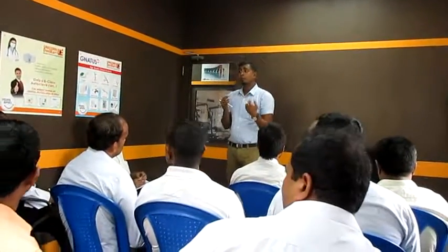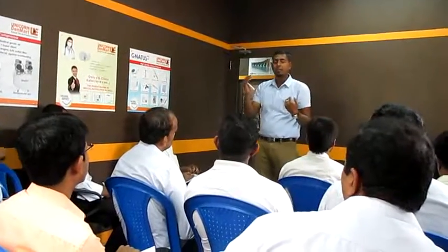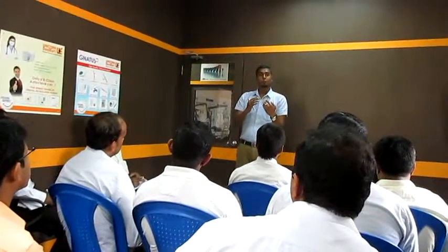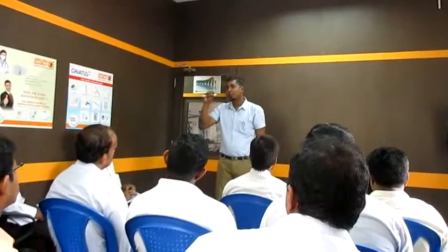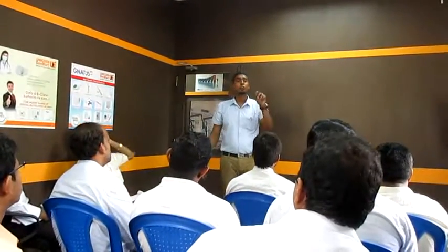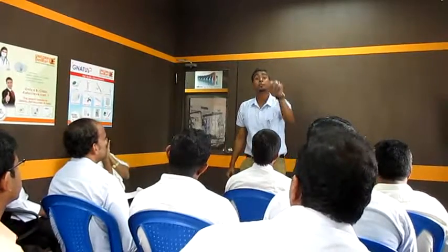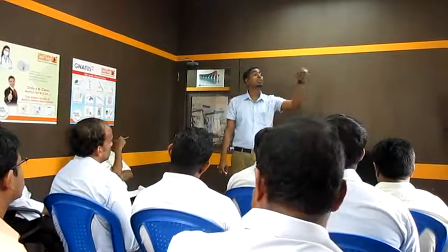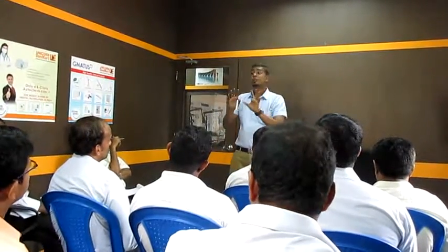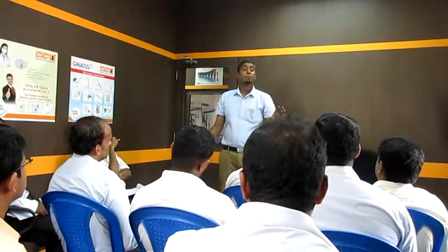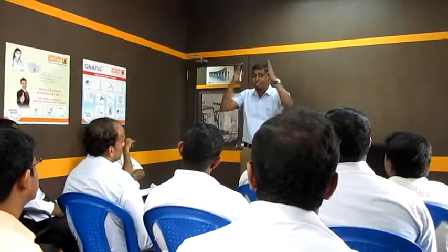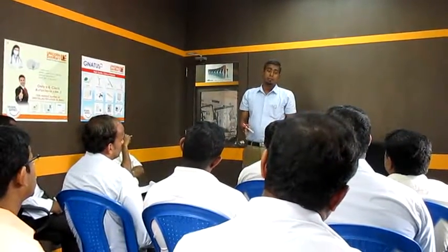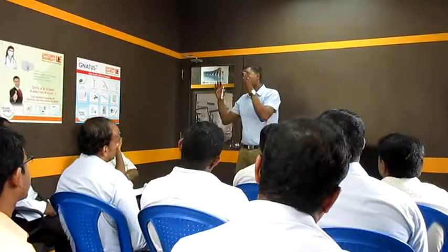For time, the calibration method, yes, I'm coming to that part. For time also, you have set 0.08 on the monitor, right? But actually your machine is exposed for 0.10 or 0.06. There is timer linearity failure, timer failure. This is the problem which has to be encountered, which has to be addressed.